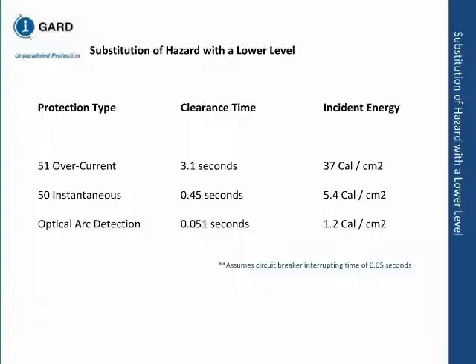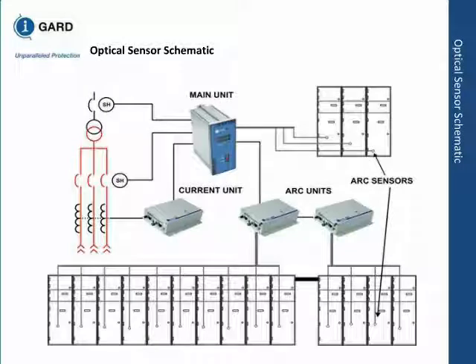This is how optical arc detection works. You have arc sensors in every cubicle, and then a current unit. It gives a signal to a main unit to trip. It's very fast, where process continuity is not the main concern. This is a very fast method available.